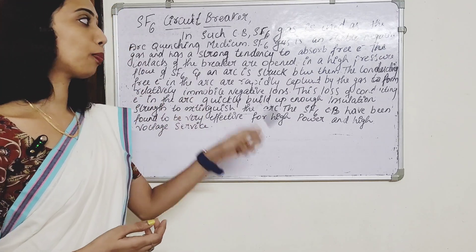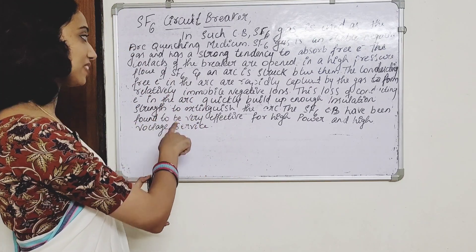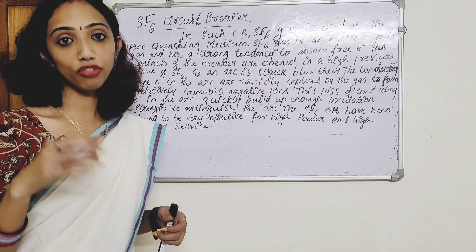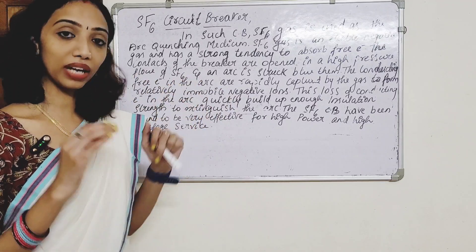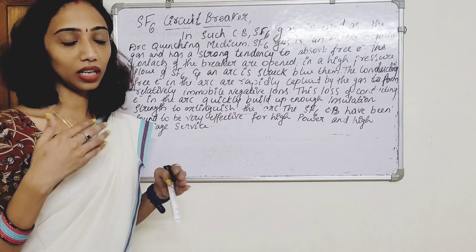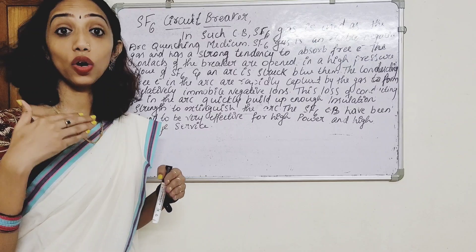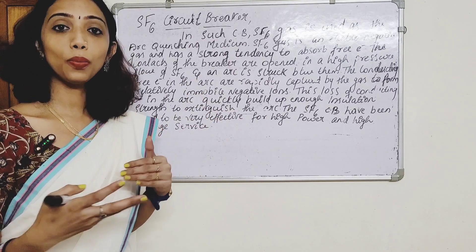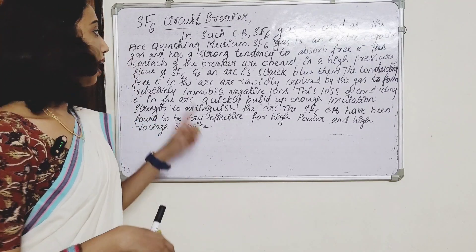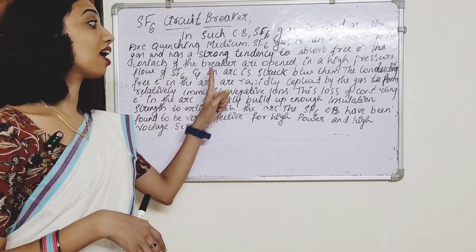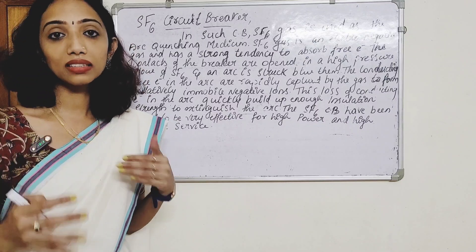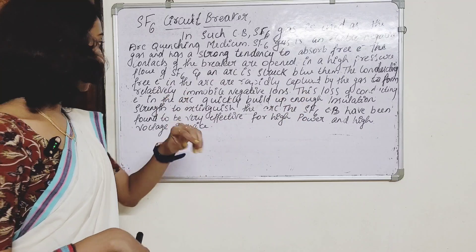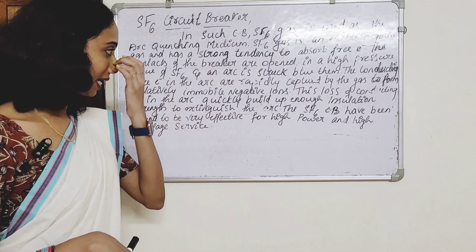The contacts of the breaker are opened in high pressure flow of SF6 gas, and an arc is struck between them. The SF6 gas flows at high pressure as the contacts open. The moving contact separates from the fixed contact, and the arc is struck between them. The free electrons in the arc are rapidly captured by the gas to form relatively immobile negative ions.